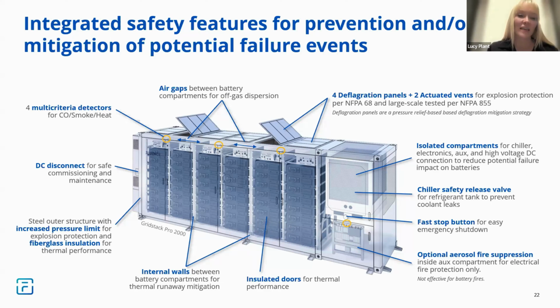Within the system itself, both the internal walls and the external walls are all fire rated. So that means that we're going to try and contain, or we will contain it within this unit. With the newer systems we have, the SmartStack, and with some of our older Cube systems, we have further modularity within the enclosure itself. The design of that is to minimize impact. Ideally, within the new product, the SmartStack, you should only see one rack or one battery pack at a time that would be lost in the case of one of these events. So you're trying to minimize that spread and the number of batteries that are involved. If we go to the next slide.